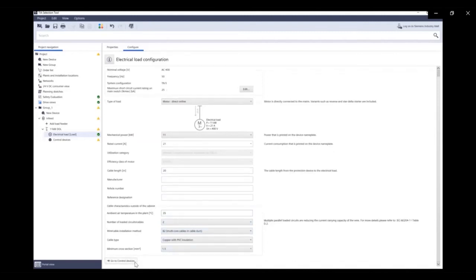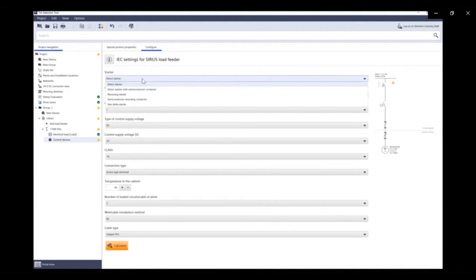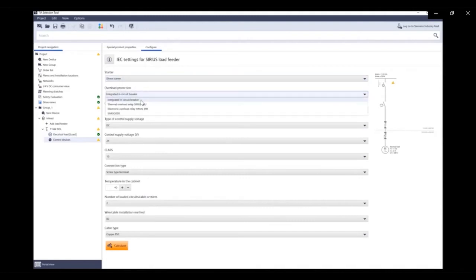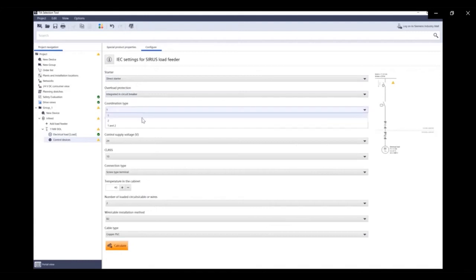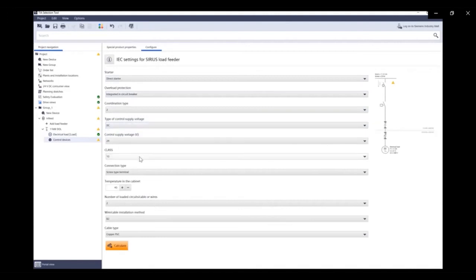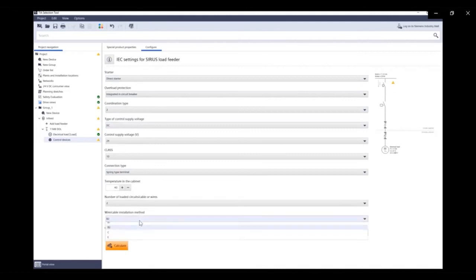So cross-check on the connections, the application direct starter, protection, circuit breaker included, coordination type 1 or 2, control voltage, whether it's DC or AC voltage, I choose 24 volt DC, class, screw or spring terminal connection, temperature in the cabinet itself, number of loads in the circuit, and the installation method.